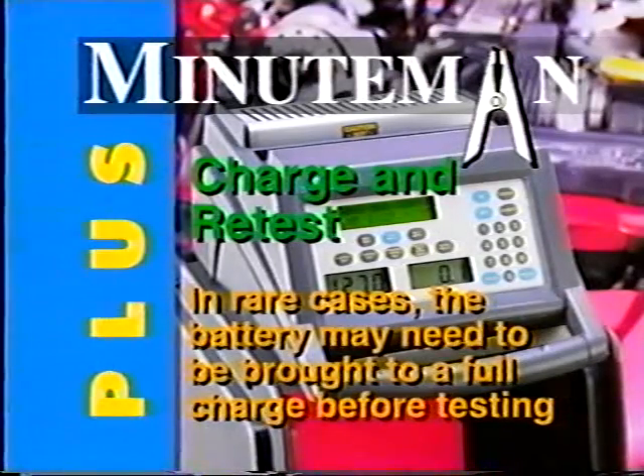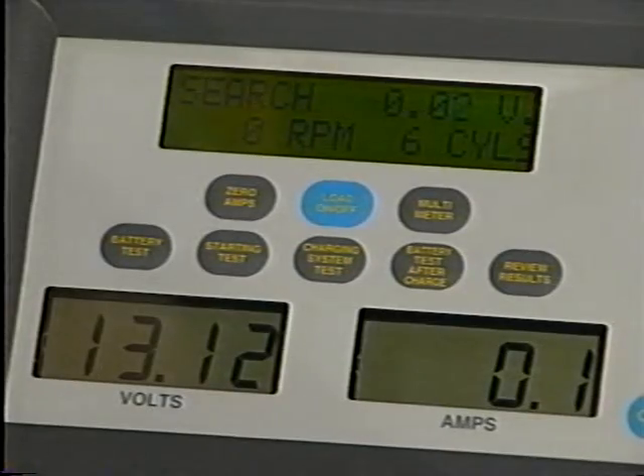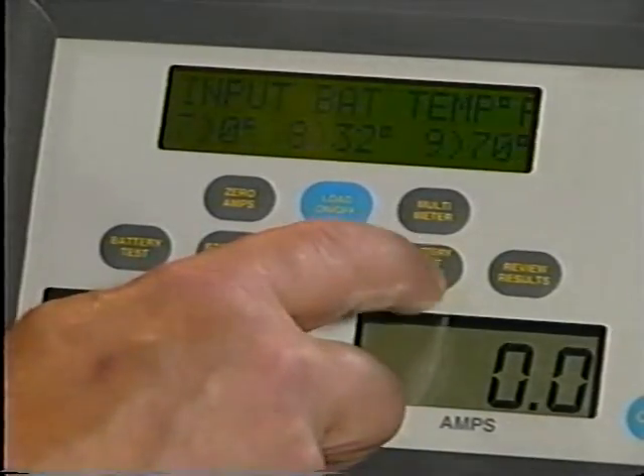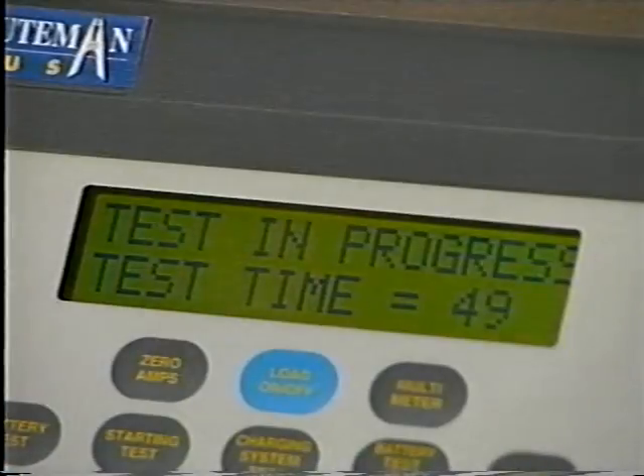In rare cases, the battery may be in a condition where it's impossible to analyze it without it first being fully charged. In this case, bring the battery to a full charge and let it stabilize in accordance with the battery manufacturer's specifications. Then, retest the battery by selecting Test After Charge. The Minuteman Plus will take into account that the battery has just been fully charged prior to the test, and it will adjust the results.